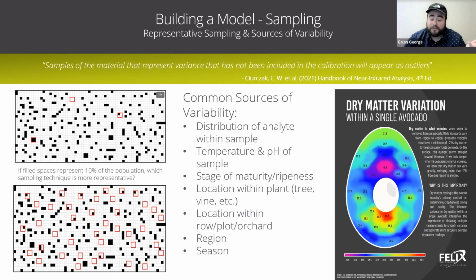And then as far as seasonality is concerned, there are multiple ways that we can go about building seasonality into our model. But there are research articles out there that show that after about 3 seasons' worth of data within your calibration set, the 4th season that you go to use the instrument, it will predict fairly accurately and won't require as robust a yearly update as you would if you try to use a single-season model to predict a 2nd season. So the more seasons you have built into your model, the more robust it's going to be. And model robustness is the ultimate goal. Robustness being the ability of the model to predict data that is not built into the calibration data set of the model.